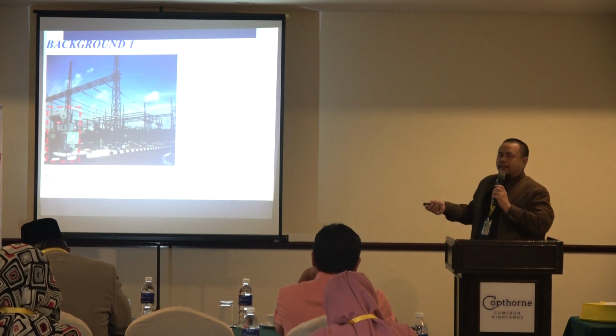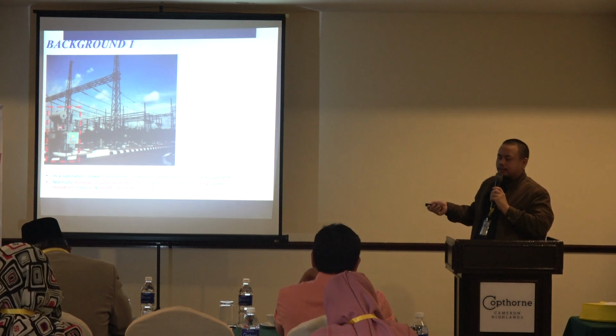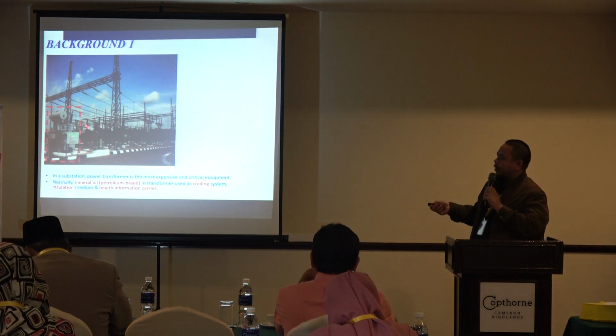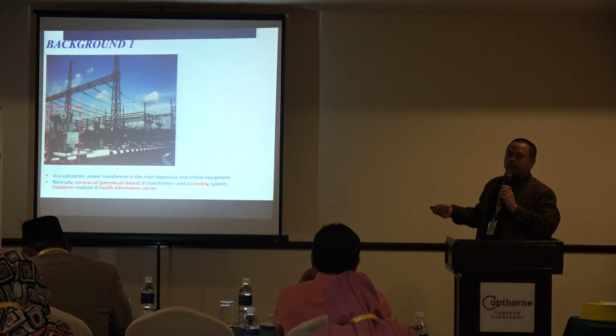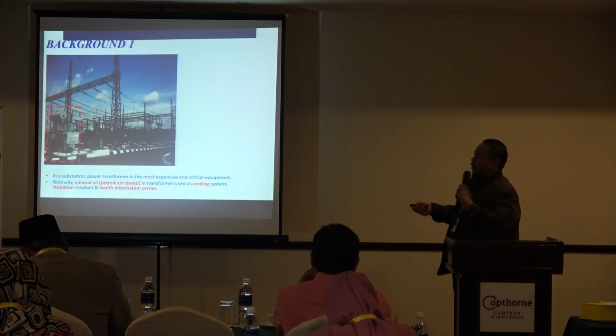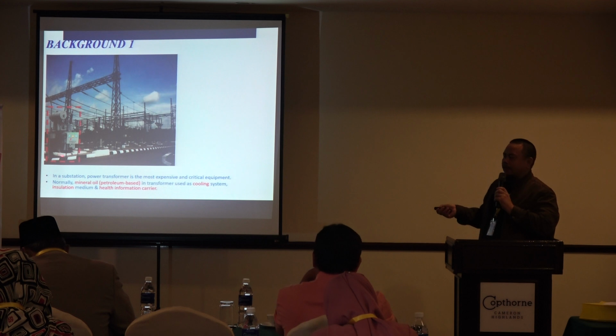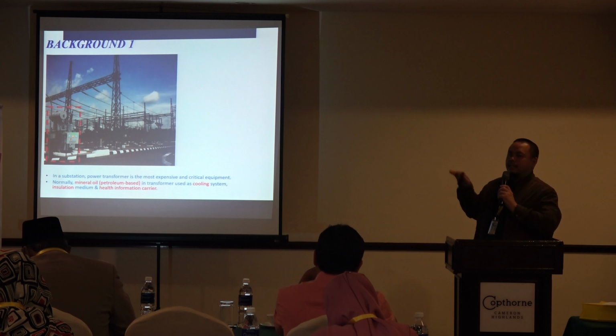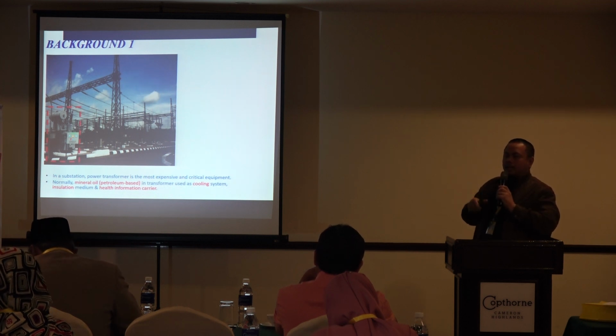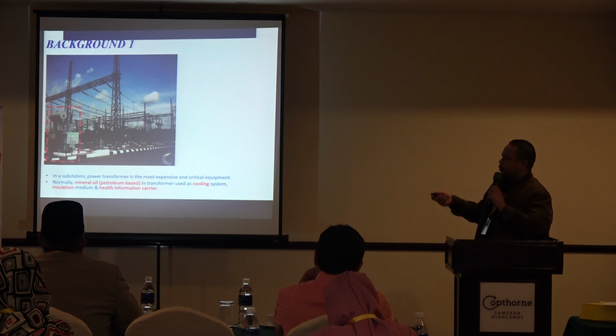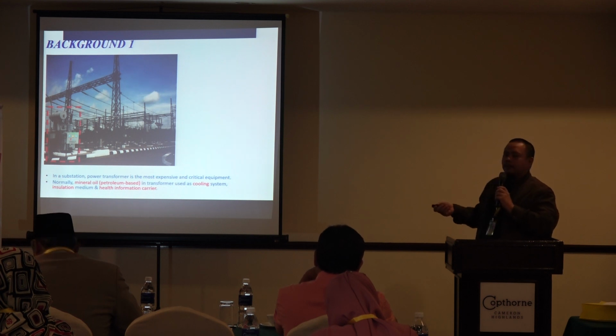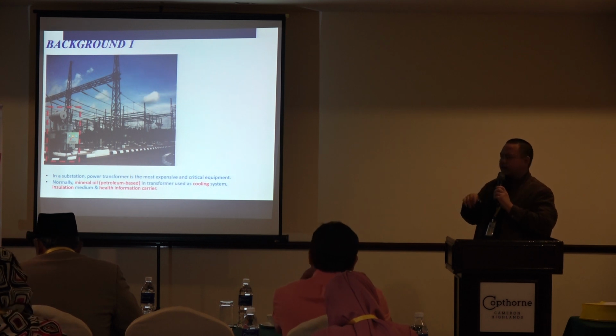Currently in TNB, a utilities company, they are using an oil immersed power transformer. It means that in the transformer itself we have an insulating oil inside, which gives the insulation of the high voltage inside the transformer. Second, it becomes a coolant in the transformer, and it is also an information carrier on the transformer health index.